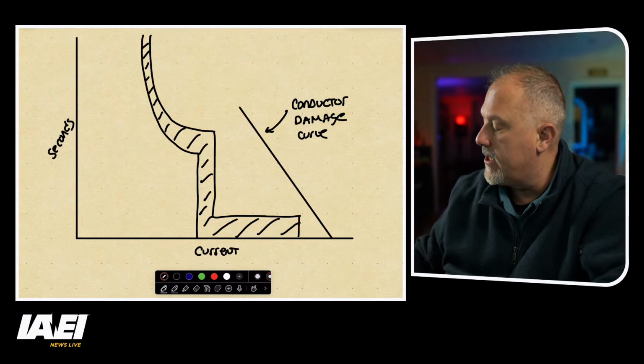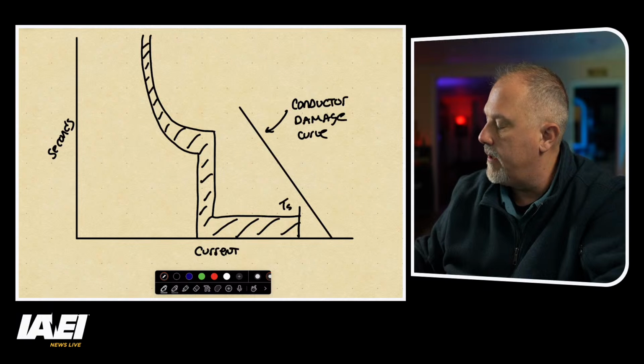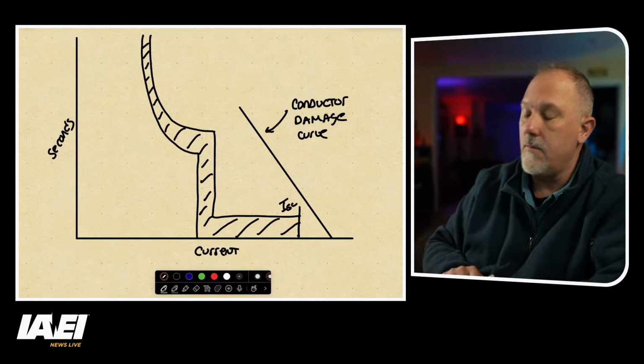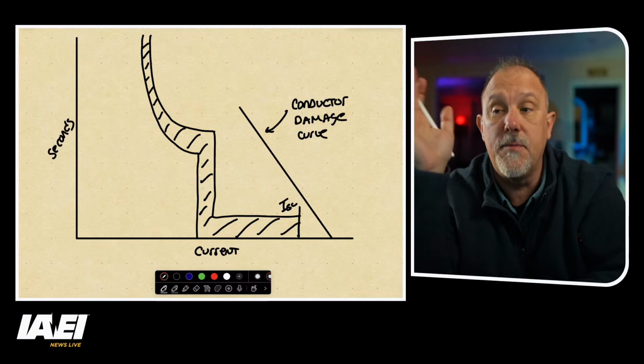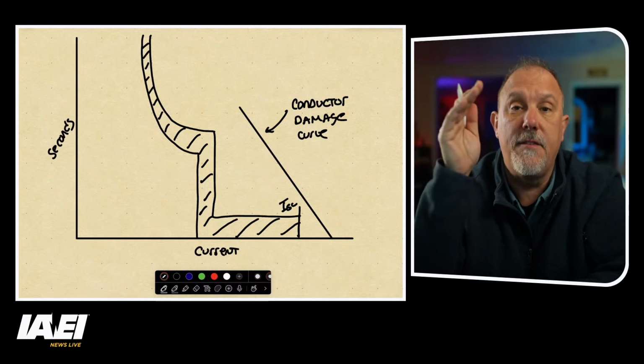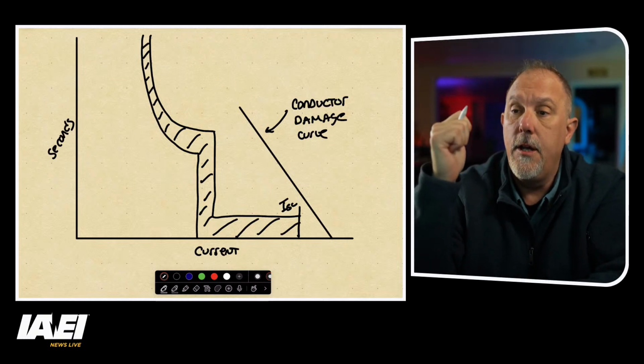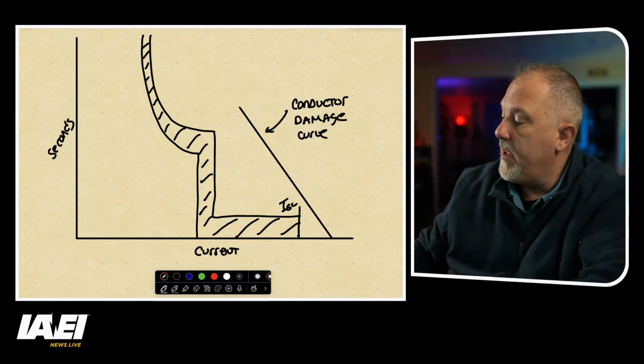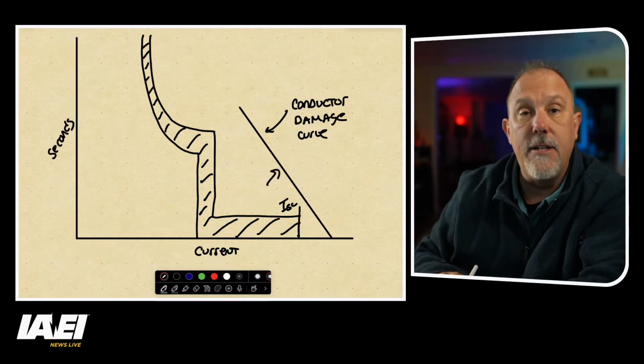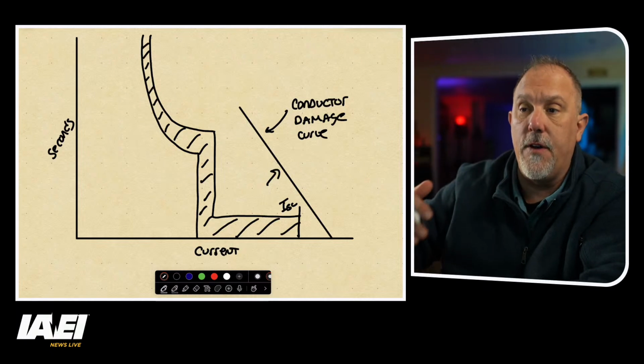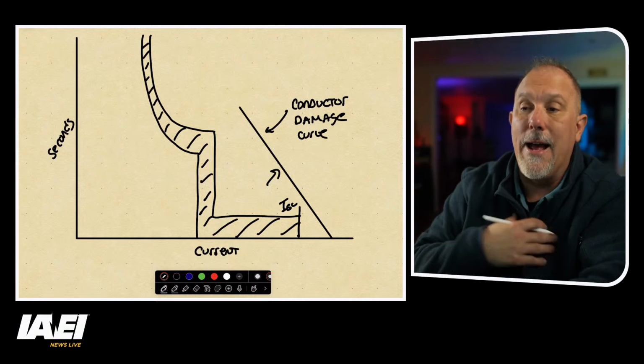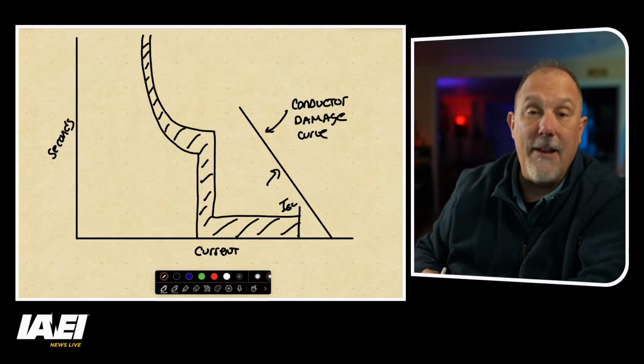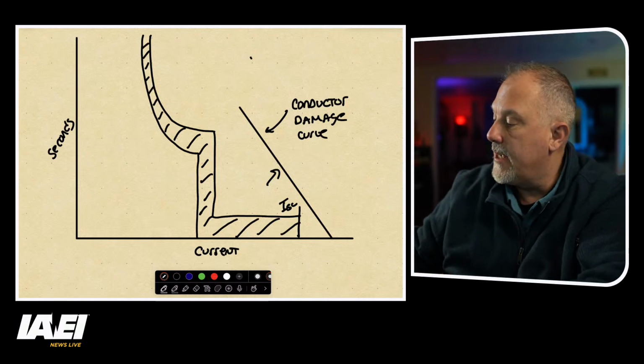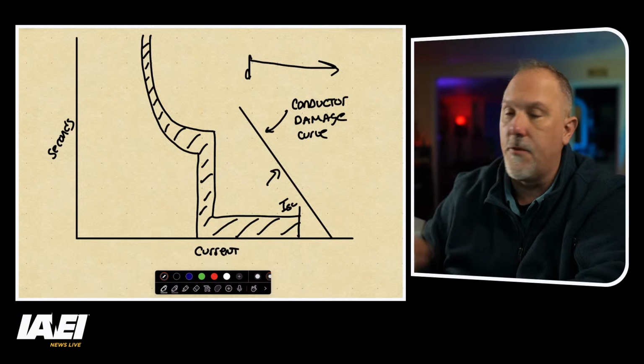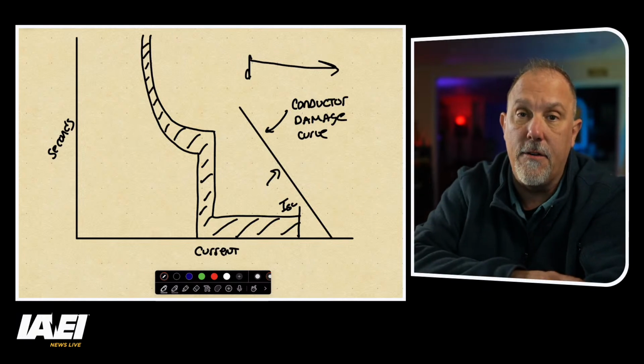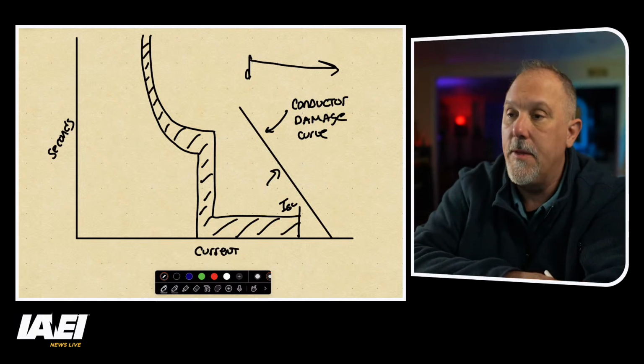And let's say we cut this off at I short circuit. Right? So now what that tells me is my overcurrent protective device, this circuit breaker, is going to open before the current gets into the damage curve of the conductor. Now, what I showed, in reality, this conductor damage curve is much further to the right on the TCC curve, more so than you would think.